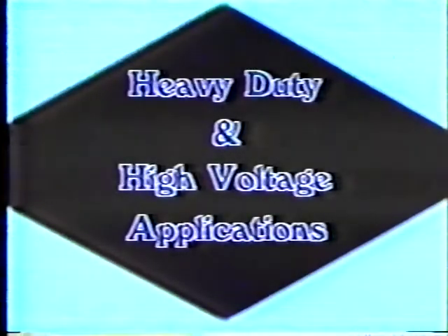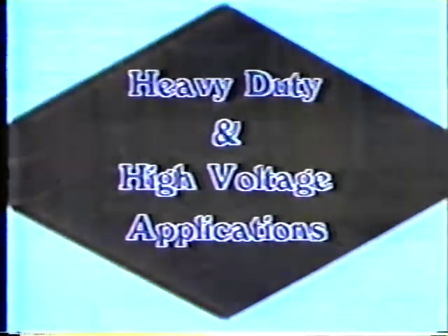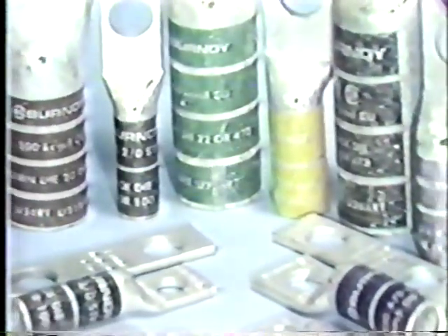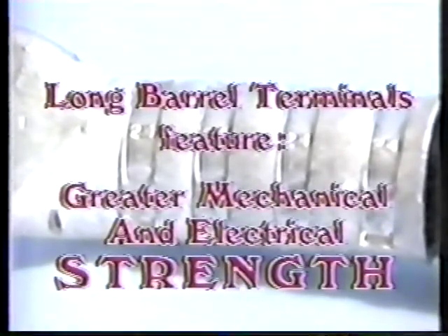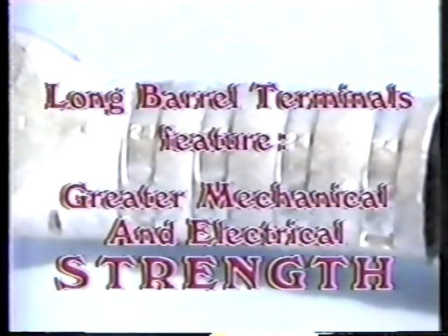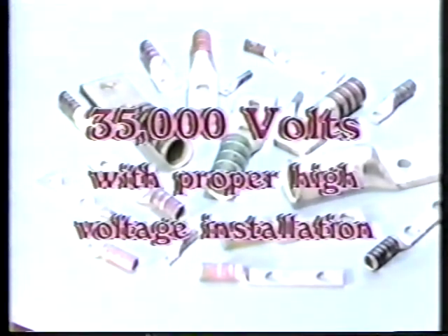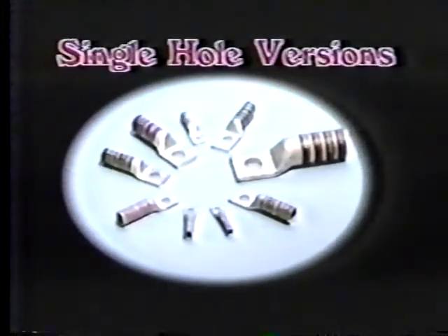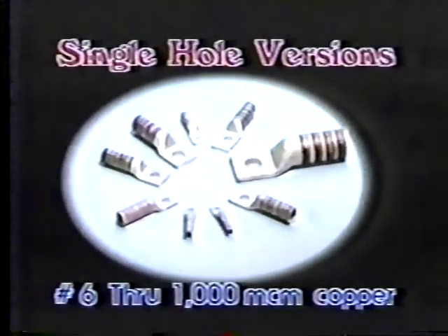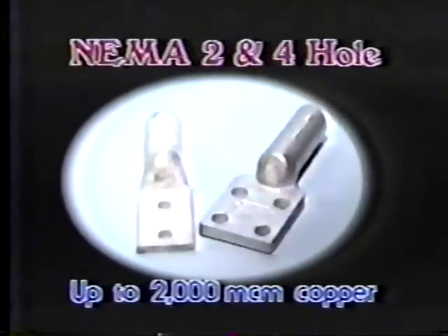For heavy-duty and high-voltage applications, Burndy provides a complete line of long barrel terminals. These terminals feature a closed transition to minimize moisture entry and greater mechanical and electrical strength resulting from twice the crimping area. With a proper installation, these terminals are acceptable for 35,000 volt applications. Burndy's long barrel terminals are available in single-hole versions for copper conductors ranging from number 6 through 1,000 MCM. NEMA 2-hole and 4-hole versions are also available for conductors up to 2,000 MCM.